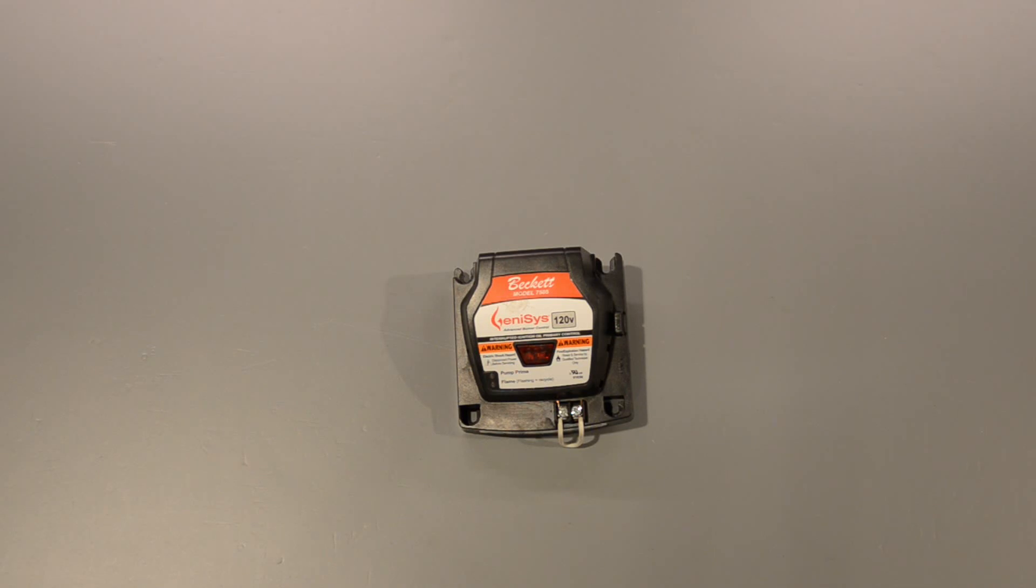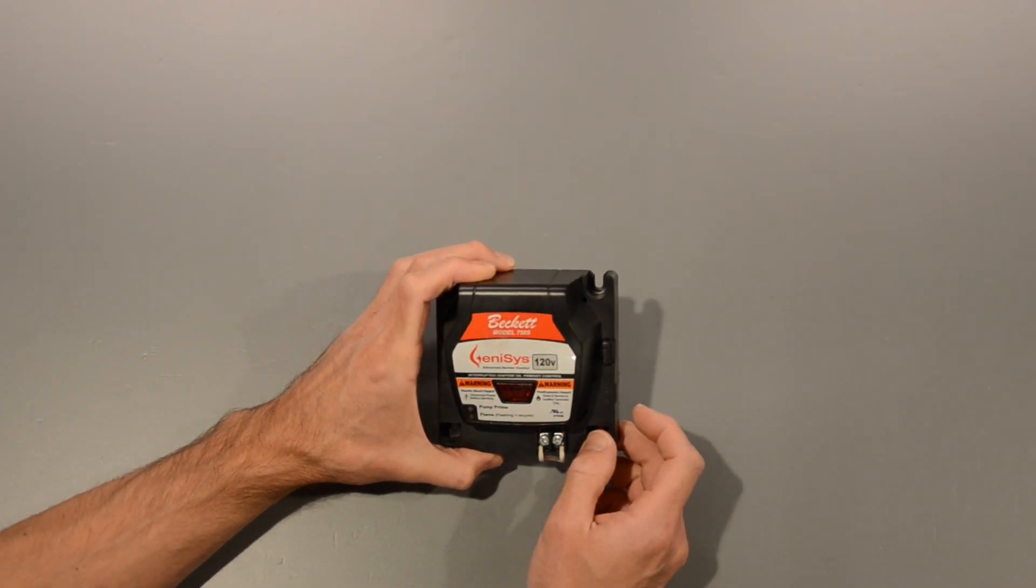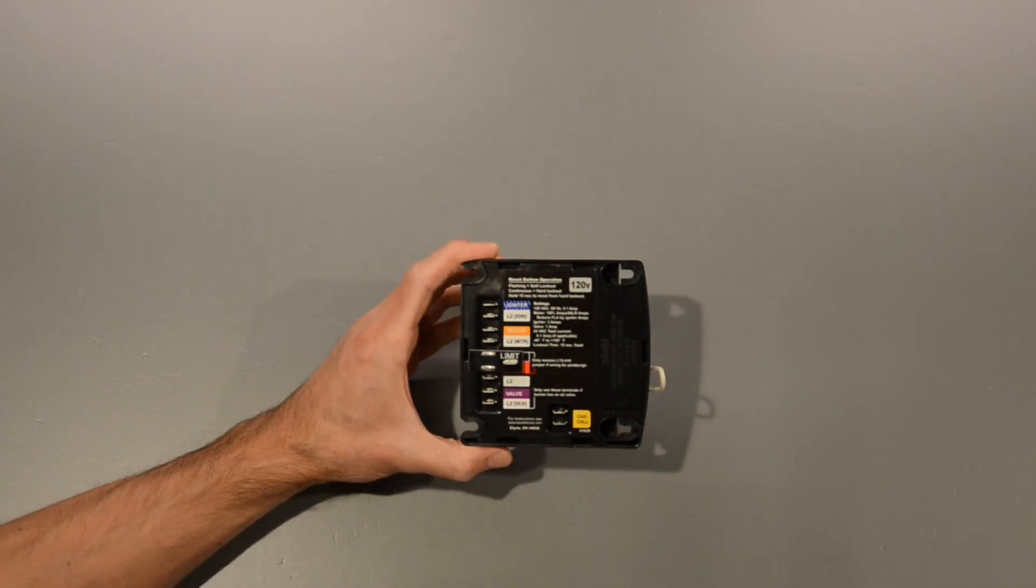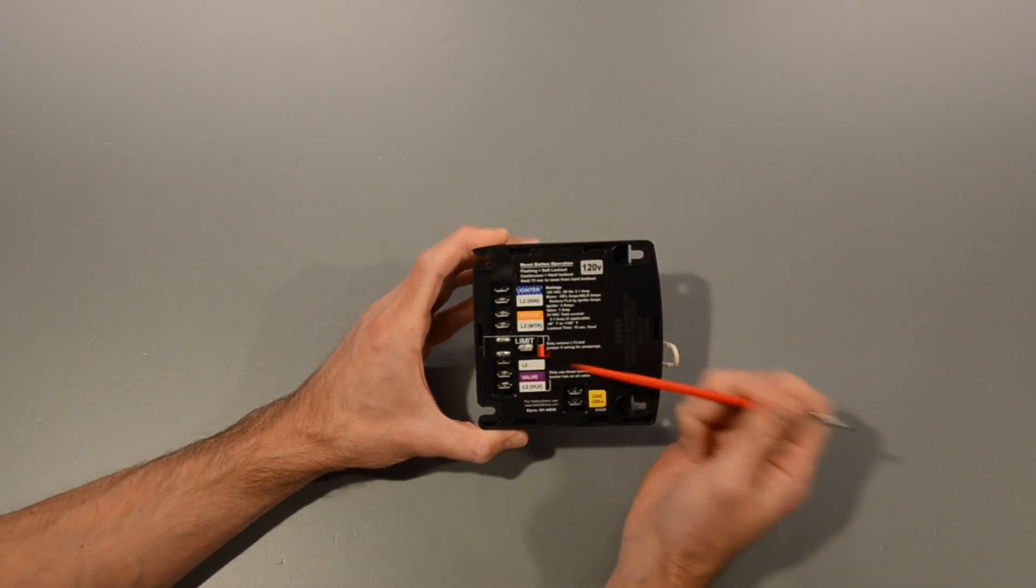The burner for my oil-fired boiler was tripping out on safety, and after some troubleshooting I determined that this burner control was faulty. This is a Beckett 7505, and the way this works is when there's a call for heat, 120 volt AC power is applied to these terminals.